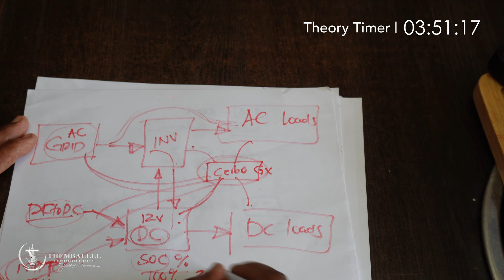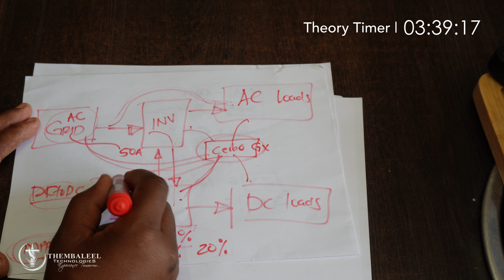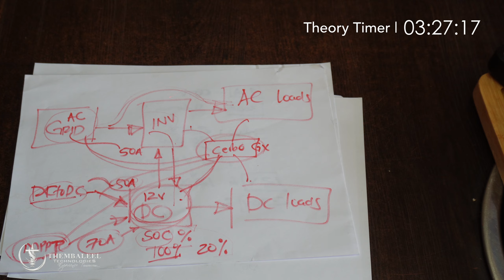If the battery is, say, at 20%, we need as much power as possible to reload our state of charge. So it will draw all the power, 50 amps in our case, from the grid, all the power from our DC to DC, and all the power, 70 amps, from our MPPT. All this power has to be thrown into a battery that can handle such current so it can get to a higher state of charge in a short space of time. All that's determined by the GX.